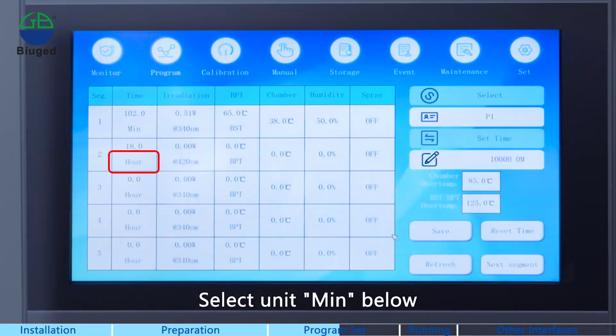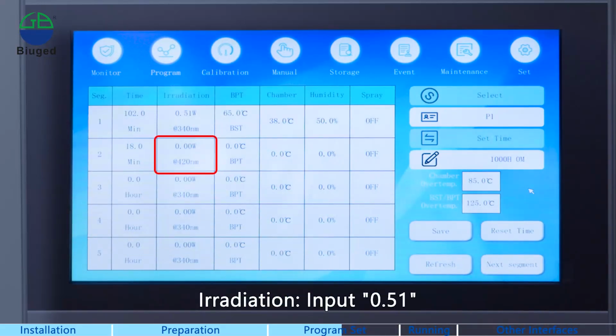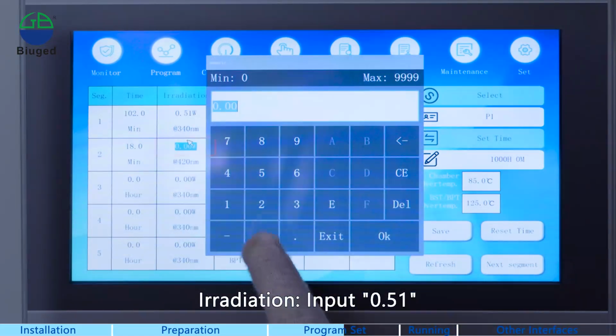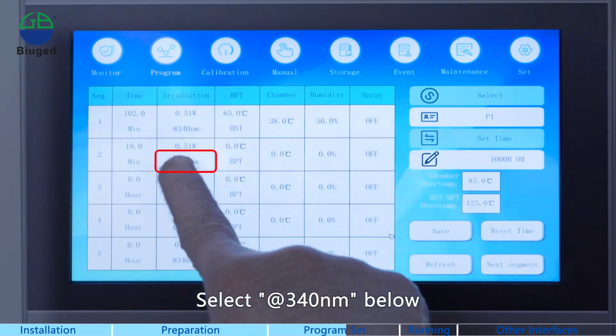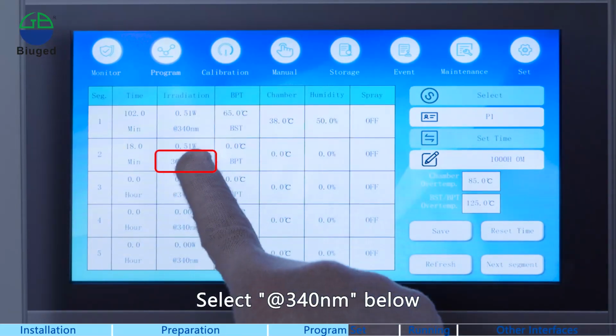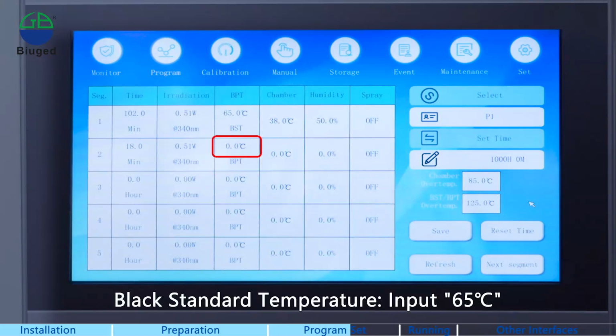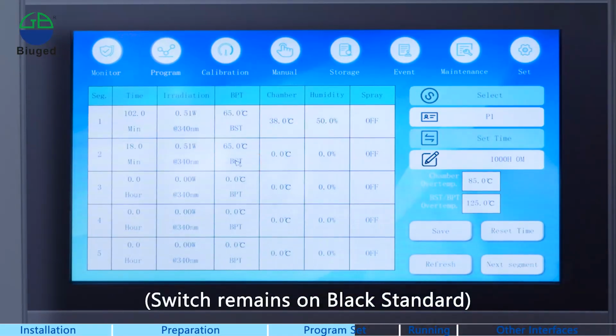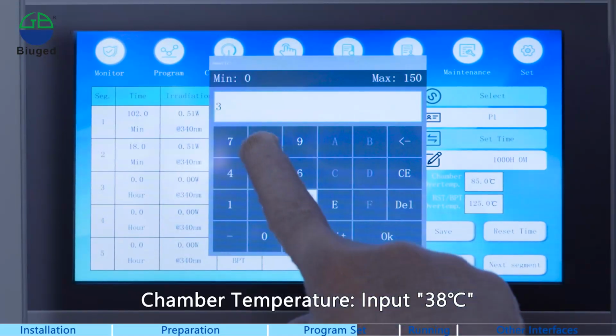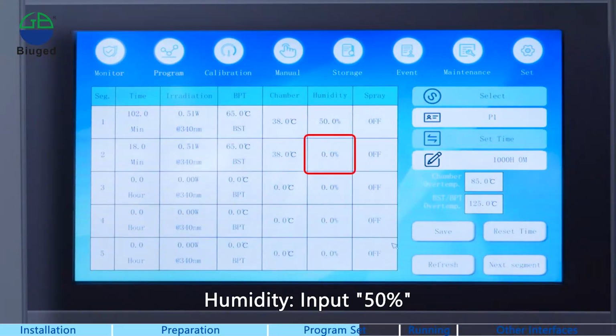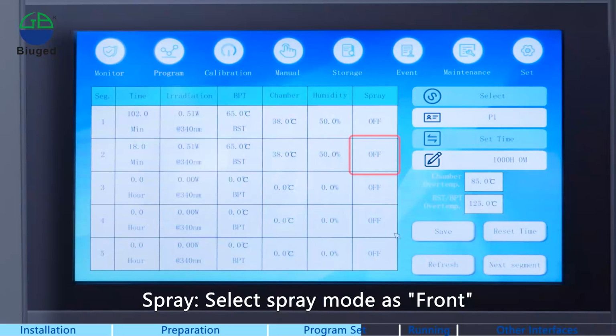Select unit minutes below. Irradiance, input 0.51. Select at 340 nm below. Black standard temperature, input 65 degrees Celsius. Switch remains on black standard. Chamber temperature, input 38 degrees Celsius. Humidity, input 50%. Spray, select spray mode as front.